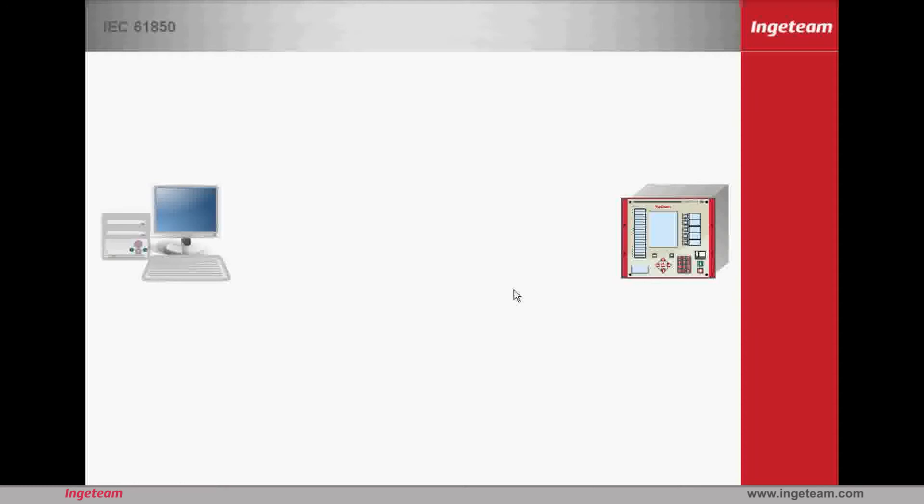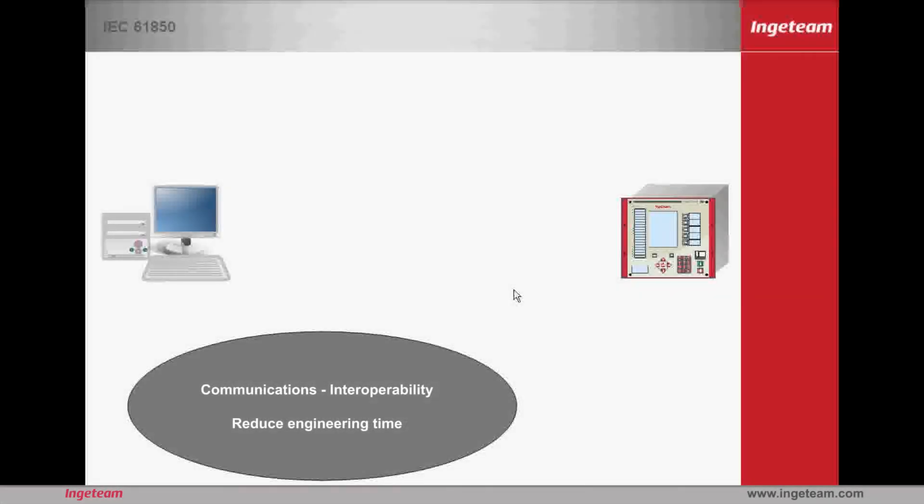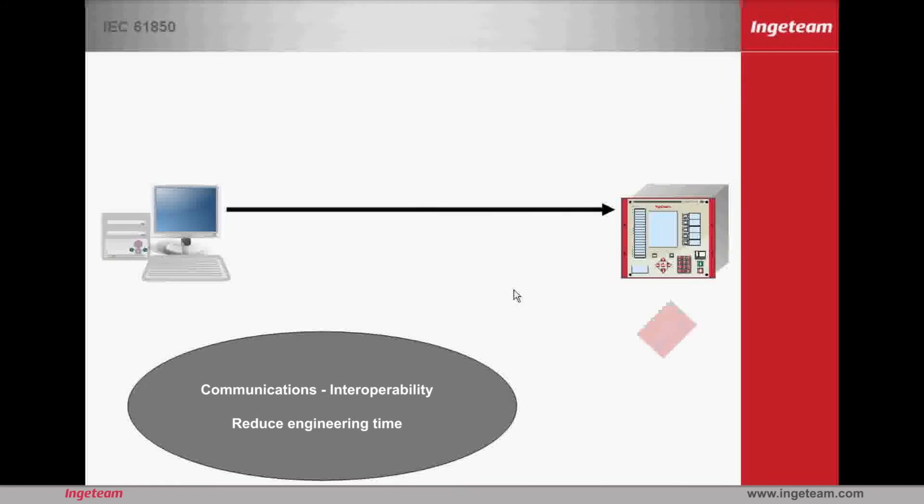The IEC 61850 standard has two main objectives. The first is to provide interoperability between manufacturers. The second objective is to reduce engineering times. These days, there are many communications protocols and many of them are standard. The aim of facilitating interoperability is common to all of them, but the IEC 61850 standard has provided an added value in that the information models are textual. This means that by analyzing the information model exchanged between two devices, someone who knows the standard without necessarily knowing these devices is able to interpret what the information means. The data does not consist of indices in memory maps, but instead textual names that express the information to be represented.